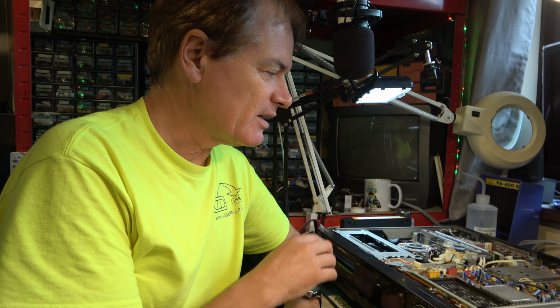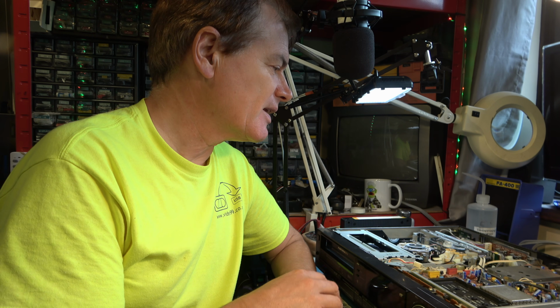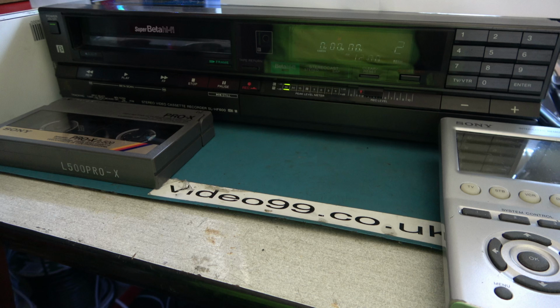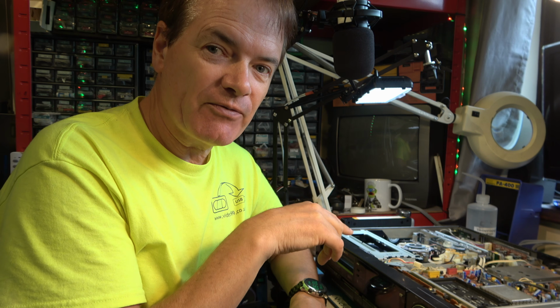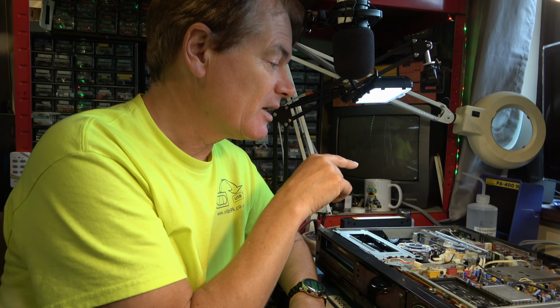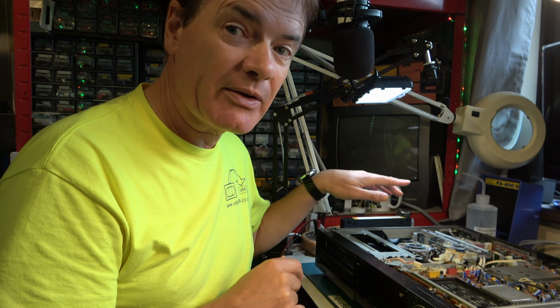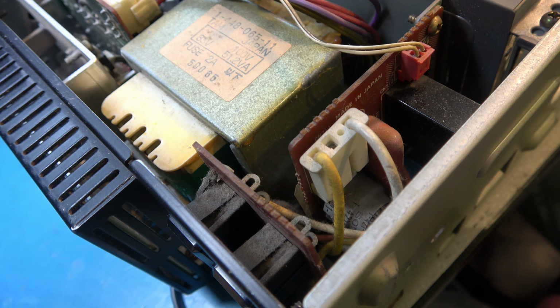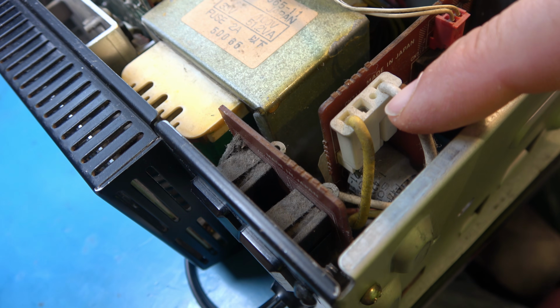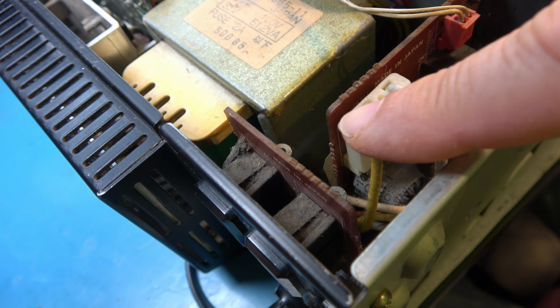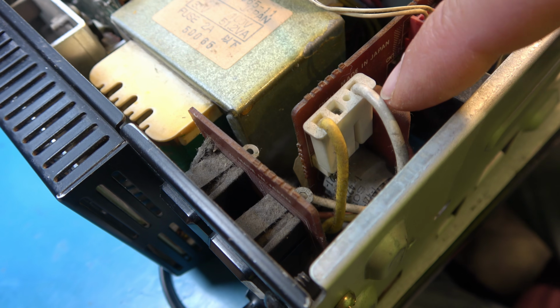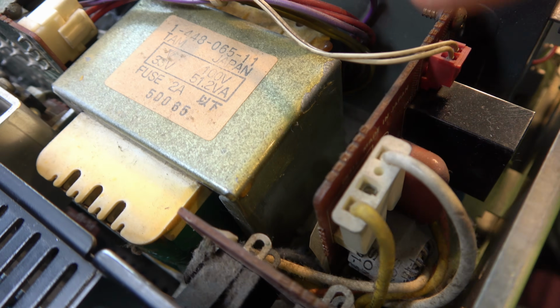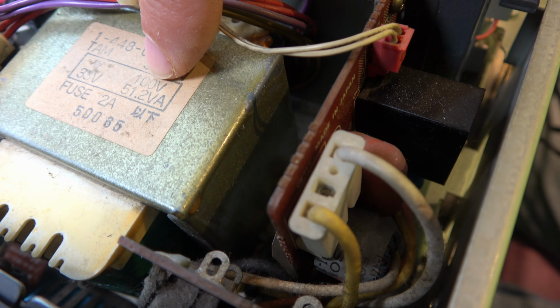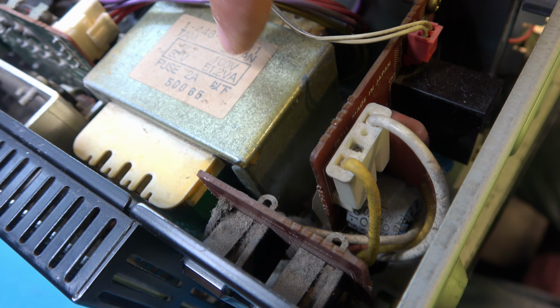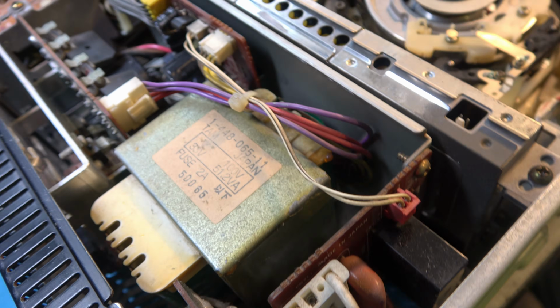So let's first see what we can do about the mains voltage. Now, the HF600, which is the other SuperBeta machine which I was working on a few months ago, you can actually reconfigure that for different voltages. There's different tappings on the transformer. I'm not seeing that here, so let's have a look at the power supply. Oh dear, this is not looking so good. This is the input to the transformer, and there's only the two wires, so it's not like there's different tappings coming onto this. And then the transformer itself actually says 100 volt, so the only thing you could do is change the entire transformer. Oh, that's inconvenient.